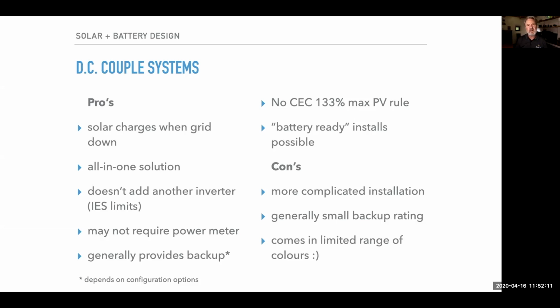Many DC coupled systems are an all-in-one solution, so they can have solar connected and grid connected all in the one package, and they will work independently of the grid and charge batteries. It doesn't add another inverter to your installation. What I mean by that is, IES limits, inverter energy systems limits, are written into our grid standard 4777 Part 1, which is the installation standard for inverter systems. It says that the maximum inverter energy systems per single phase installation is 5 kVA, roughly 5 kilowatts. Now, if you've got a 5 kilowatt solar inverter and you want to add batteries, and you try to add an AC coupled battery, it's probably got its own 5 kilowatt inverter built in. So now you've got 10 kilowatts of inverter energy systems.